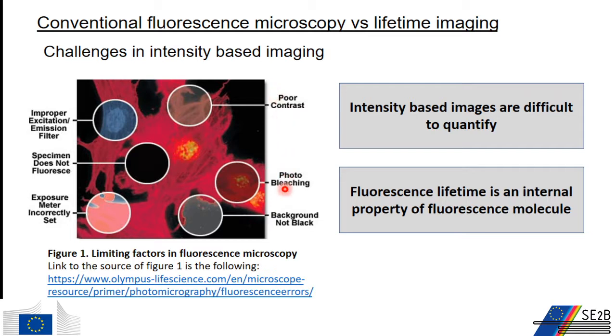Biological samples often need to be measured from several seconds up to several minutes. However, for such long exposure times, the bleaching of the fluorescence is also a very common problem. Inhomogeneous probe concentrations in the specimen can also induce variations in fluorescence intensity. Most of these shortcomings can be relatively easily overcome by using the fluorescence lifetime to construct the image of the specimen.